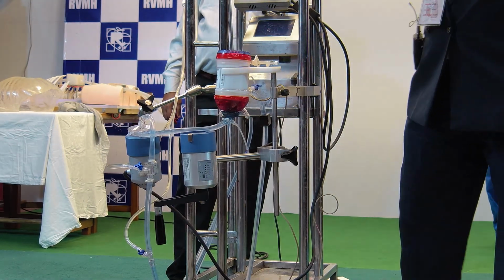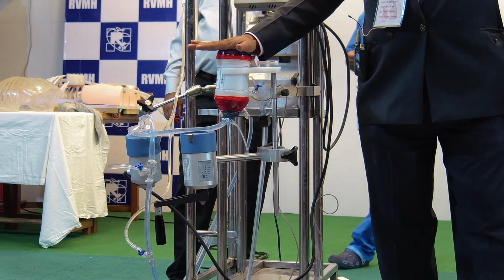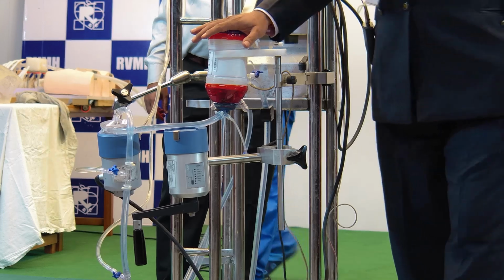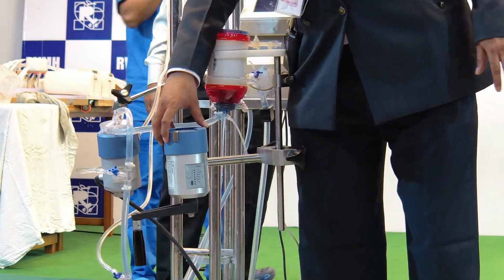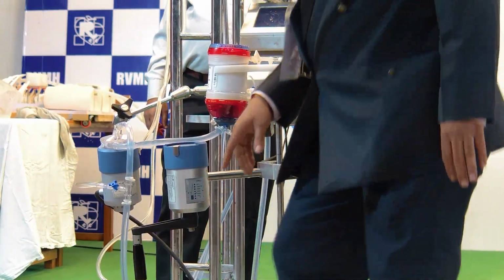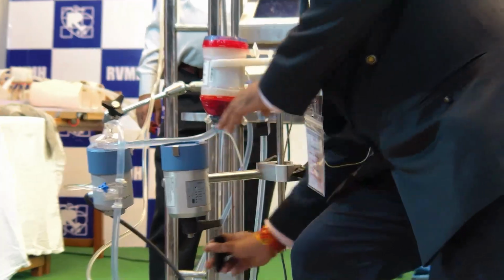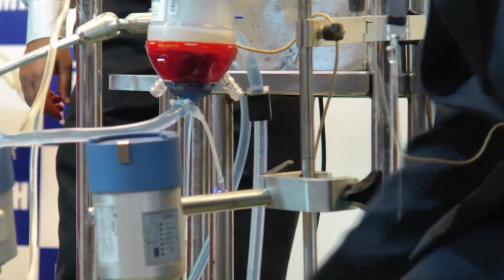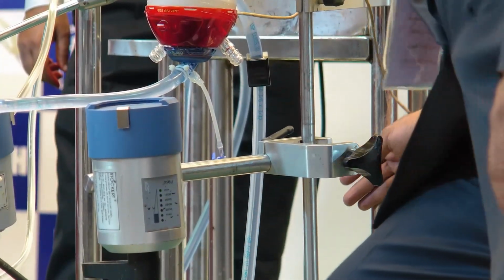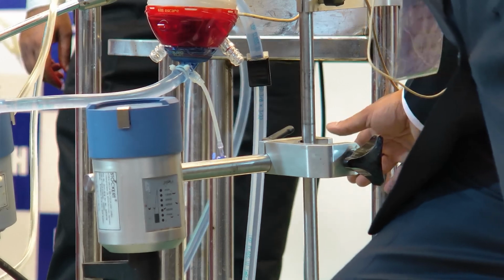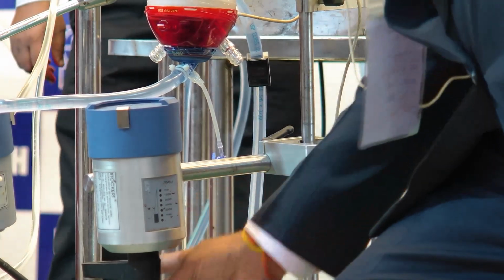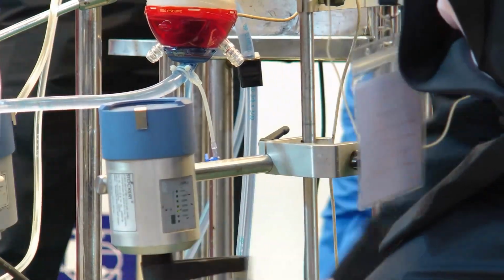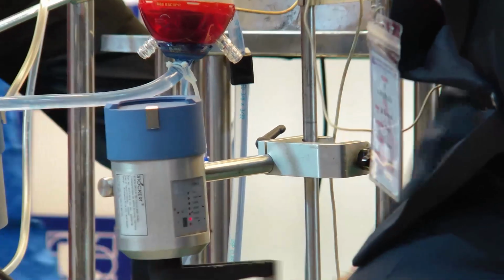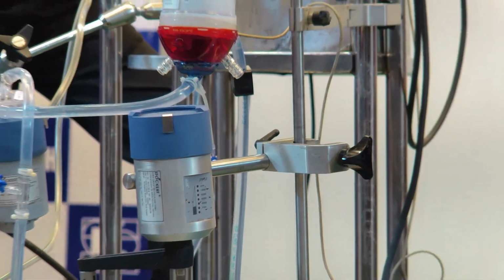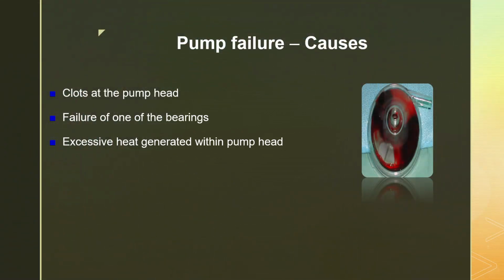So your position of the hand crank has to be something like this. It has to be below the oxygenator so that immediately you can put the pump here and you can start. Second thing, you should have free movement, you should always check the free movements. If this is too close, it will get stuck in the handles. So when you initiate ECMO, make it a habit for your staff that they should put the hand crank below the oxygenator and it should be freely moving, because these complications can occur anytime.